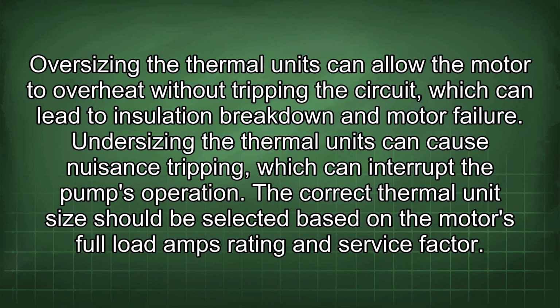Oversizing the thermal units can allow the motor to overheat without tripping the circuit, which can lead to insulation breakdown and motor failure. Undersizing the thermal units can cause nuisance tripping, which can interrupt the pump's operation. The correct thermal unit size should be selected based on the motor's full load amps rating and service factor.